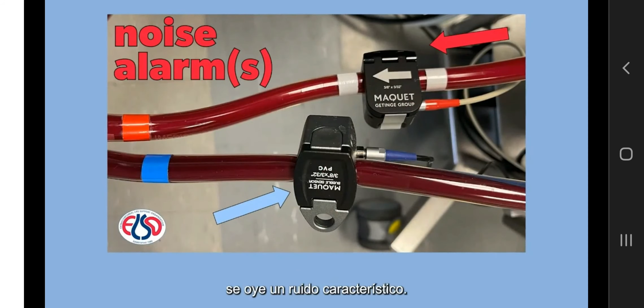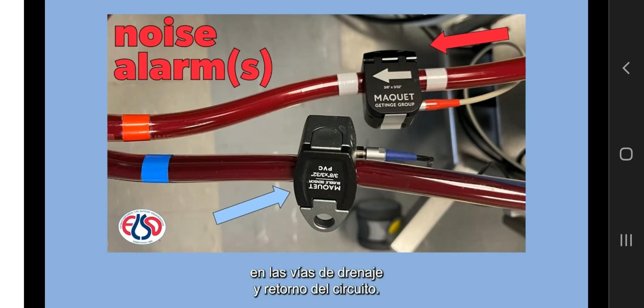When air passes through the pump head, you could hear a distinctive noise. Otherwise, air presence may activate the bubble sensor alarms. Often in current systems, we have bubble sensors on both drainage and return limbs of the circuit. Air embolism on the circuit is an emergency scenario. As air is noticed within the circuit, you need to understand the location of the air and the extension of the phenomenon, as both of these may impact on management.